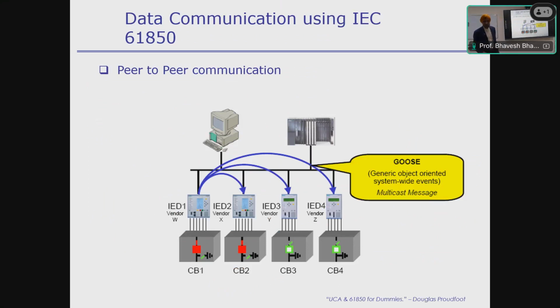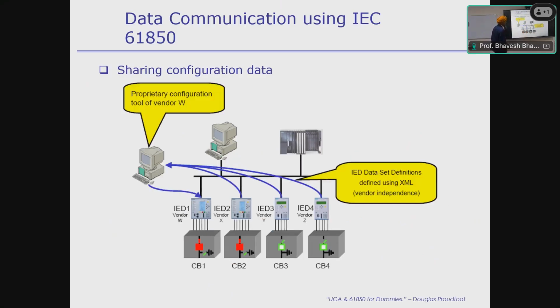Now with these, you can do peer-to-peer communication on the station bus, for example, devices can talk to each other through GOOSE messages. They can initiate any GOOSE message they want. And you can share configuration data also using the same set, although we didn't talk about configuration, but you can.